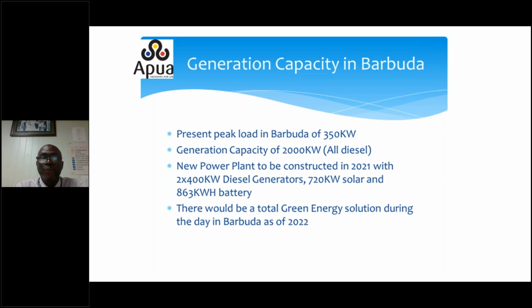You might wonder why we're going with two diesel sets. Yes, because we recognize that at night when the sun doesn't shine, there is a need, unless we're going to increase the battery amount, which is presently costly. I mean, if we want to cover the entire night period with batteries, that will be quite costly. So basically we have two diesel generators with sophisticated controls. And so we're able in Barbuda to have a green solution in the day, but in the night, you will have to use the gensets. The system is designed to be very modular, so we can add PV systems later on, we can add battery systems later. And we have incorporated all of the technical issues that were mentioned before by Roland. We have ensured that we have a well-designed system in Barbuda, the new system. Next slide, please.